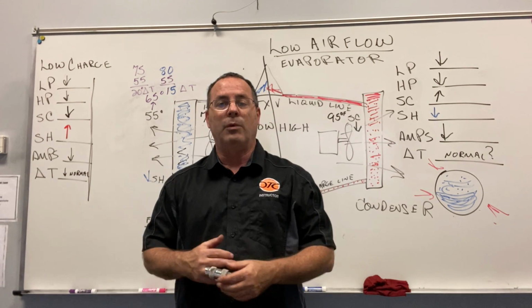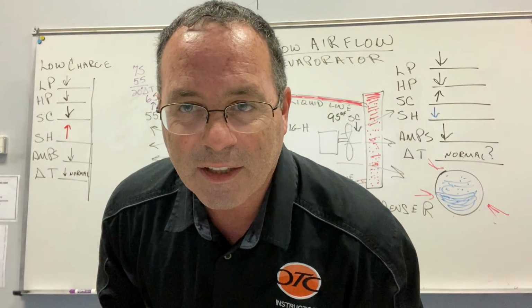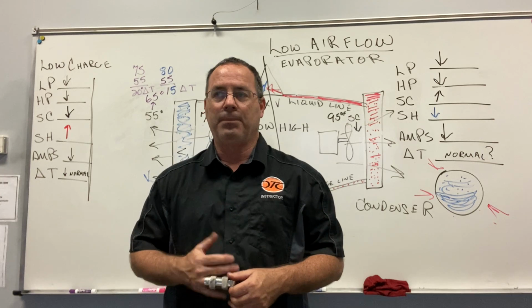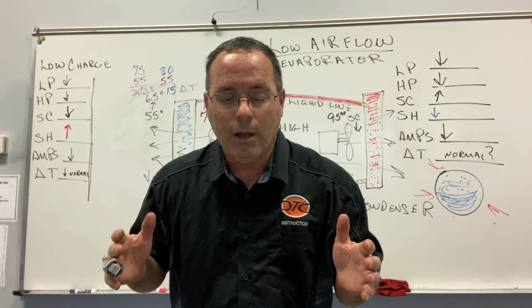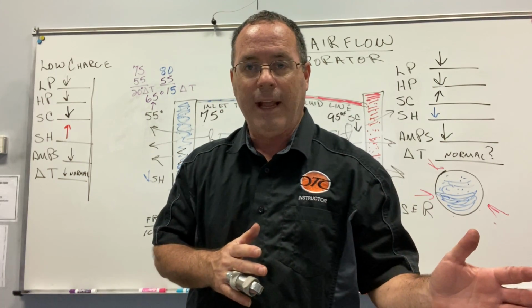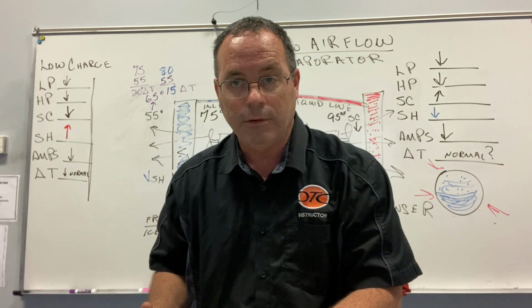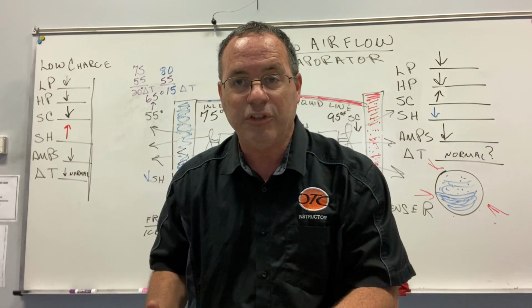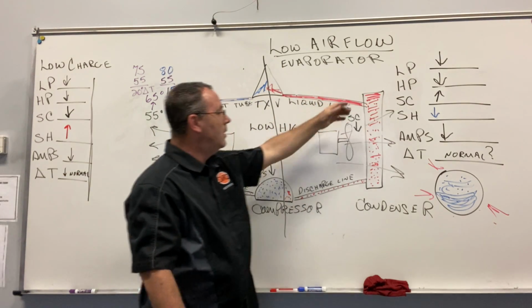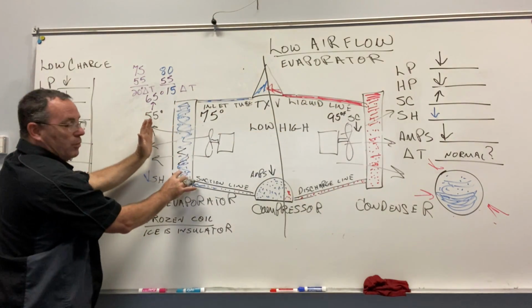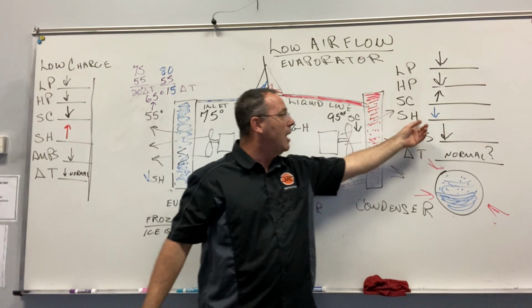So my student said, why don't you check the superheat and subcooling? He started laughing. Why are we going to do that? Maybe so we don't have to come back 10 times. So I just gave you the symptoms of a low airflow coil and a low charge. So what is the difference here? When we have low airflow, we have more liquid because we don't have energy going in, so our superheat is low.